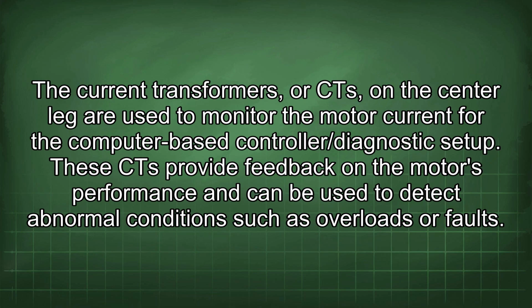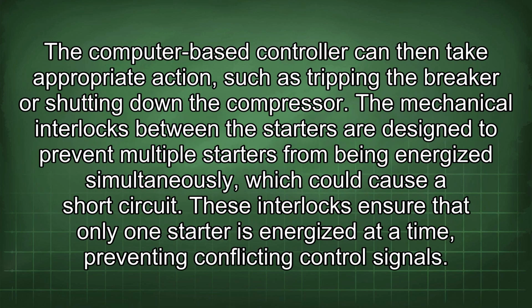The current transformers, or CTs, on the center leg are used to monitor the motor current for the computer-based controller/diagnostic setup. These CTs provide feedback on the motor's performance and can be used to detect abnormal conditions such as overloads or faults. The computer-based controller can then take appropriate action, such as tripping the breaker or shutting down the compressor. The mechanical interlocks between the starters are designed to prevent multiple starters from being energized simultaneously, which could cause a short circuit. These interlocks ensure that only one starter is energized at a time, preventing conflicting control signals.